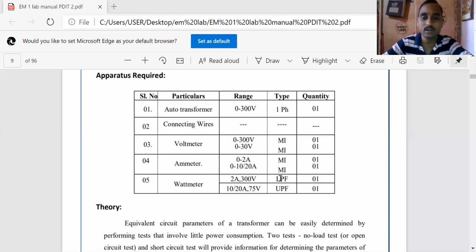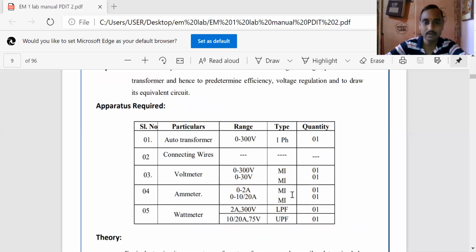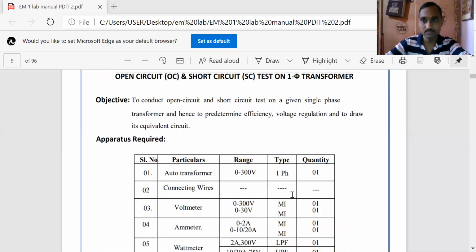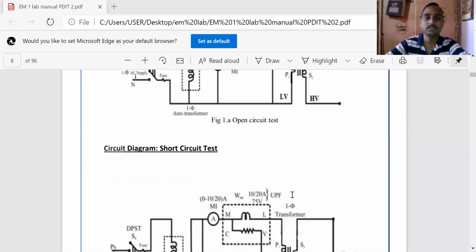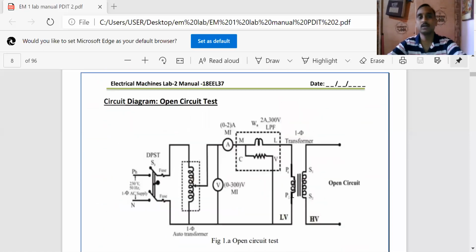This is used for the open circuit test, and the UPF wattmeter is used for the short circuit test. Its current range is 0 to 10 ampere, or you can use 0 to 20 ampere. The voltage rating required is up to 75 volts or 100 volts. That is enough. These are the apparatus required for the experiment. Now the circuit diagram: this is the open circuit test circuit diagram.